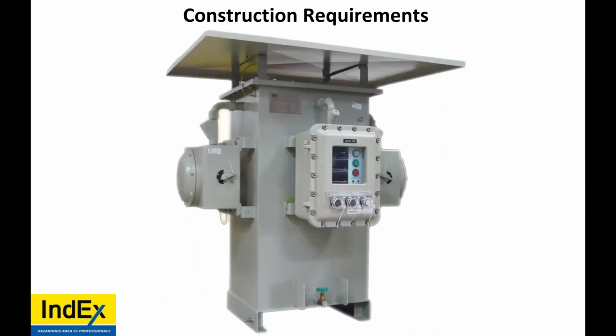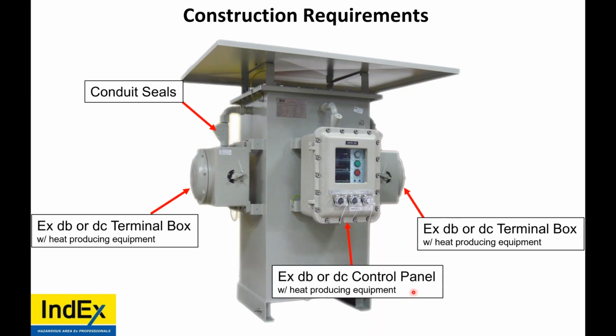So if we look at this device, I believe this is an oil-filled rectifier. Well, what do we have? Well, we have EXD terminal boxes on the left and the right, and then you have an EXD control panel with heat producing equipment here. But there's also conduit seals. Also because this enclosure is full of oil or protective liquid, whatever they filled it with.